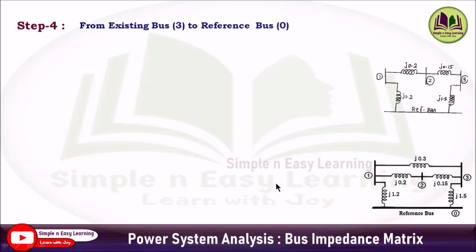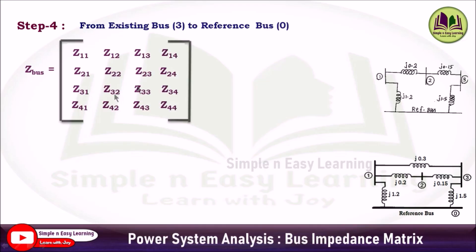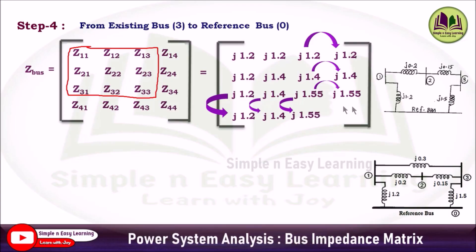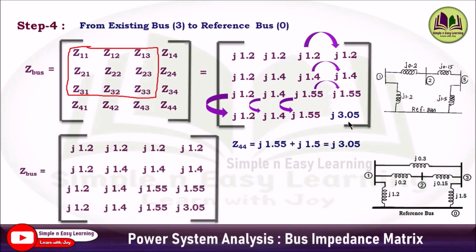Step 4: from existing bus 3 to the reference bus, considering reactance j1.5. Z-bus is now a 4×4 matrix with 16 terms. The nine terms from step 3 are substituted directly. Using the copy-paste procedure, Z14 = j1.2, Z24 = j1.4, Z34 = j1.55, and similarly for the fourth row. Z44 equals j1.55 plus j1.5, giving j3.05. The Z-bus matrix at step 4 is thus a 4×4 matrix.